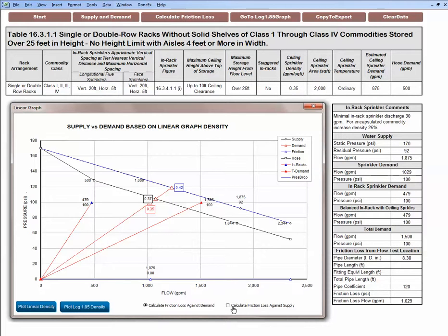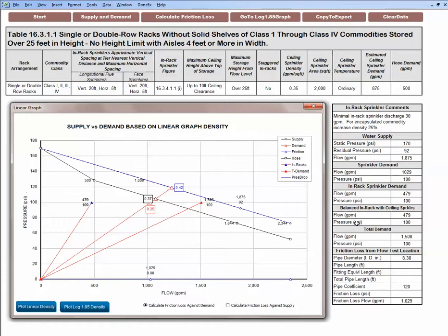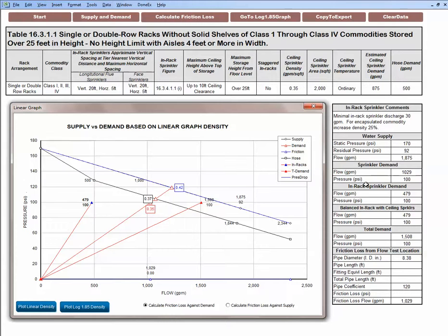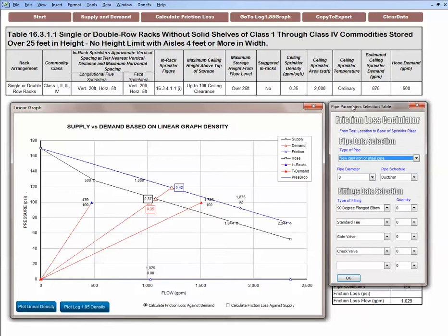I could also calculate friction loss against supply. You can see this change back and forward. I had no pressure drop. In my particular example the friction loss and the pressure demand for the sprinklers was calculated at the fire pump, so there's no friction loss to calculate. But if we need to calculate friction loss we click this button calculate friction loss and I'm going to do it to demonstrate and enter some data.